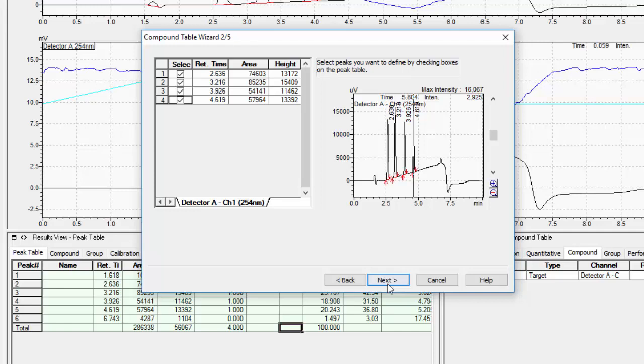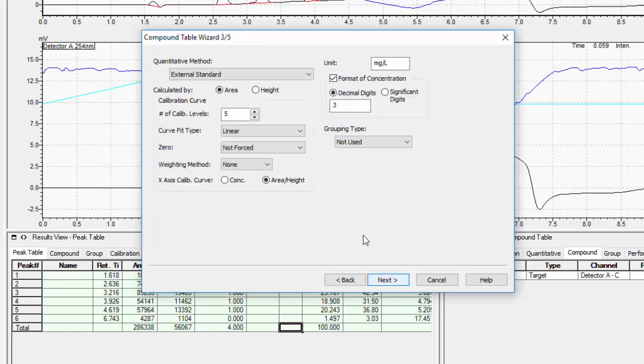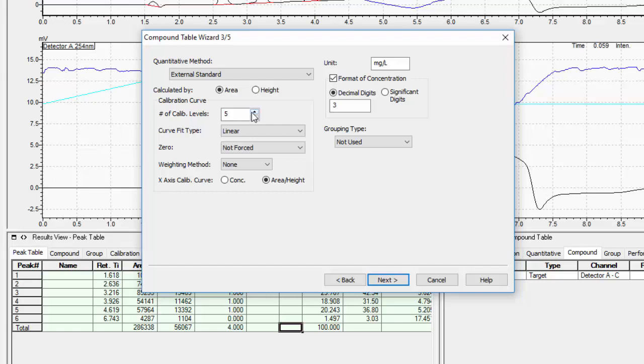Once you click next, you will be asked to enter the quantitative information. You can choose to enter this now or it can be entered in later when creating a calibration curve to quantitate your unknowns. If you choose to enter the information now, you will need to select from the drop down menu your method of quantitation, whether it be external or internal standards, the number of concentration levels you are using to create the curve, weighting and line fitting criteria, as well as units. Please note that the units are for your own reference and not used numerically when calculating the calibration curve.